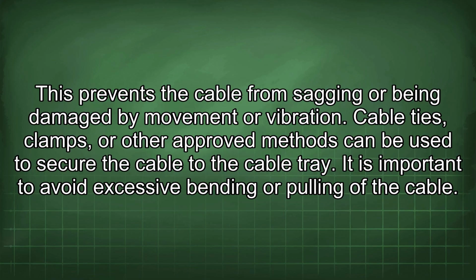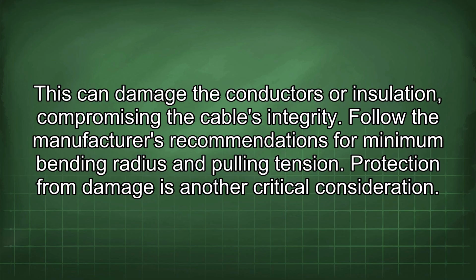It is important to avoid excessive bending or pulling of the cable. This can damage the conductors or insulation, compromising the cable's integrity. Follow the manufacturer's recommendations for minimum bending radius and pulling tension.